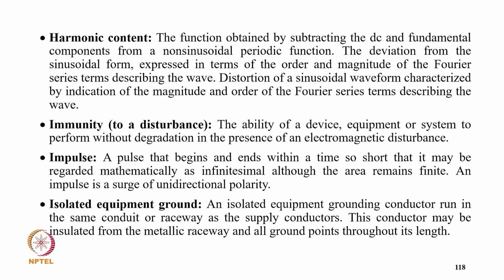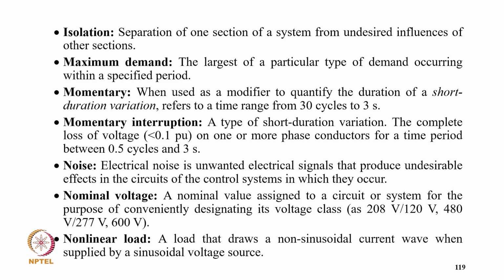Immunity to disturbance, the ability of a device, equipment, or system to perform without degradation in the presence of an electromagnetic disturbance. Impulse, a pulse that begins and ends within such a short time that it may be regarded mathematically as infinitely short, although the area remains finite; an impulse is a surge of unidirectional polarity. Isolated equipment ground, an isolated equipment grounding conductor that runs in the same conduit or raceway with the supply conductors. This conductor may be insulated from the metallic raceway and all ground points throughout its length. Isolation, the separation of one section of a system from the undesired influence of other sections.